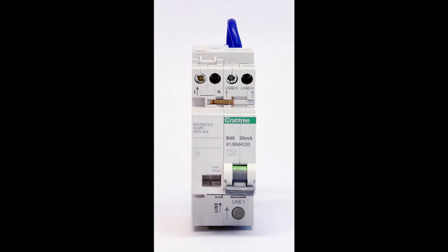Meter tails. The 18th edition also includes Regulation 522.8.5, which requires every cable to be installed in a way that avoids any mechanical strain and makes sure that there is no strain on the conductors and connections. Consumer unit meter tails are included in this requirement. This is in addition to any other requirements to provide protection to tails at the point of entry into metal consumer unit enclosures, etc.